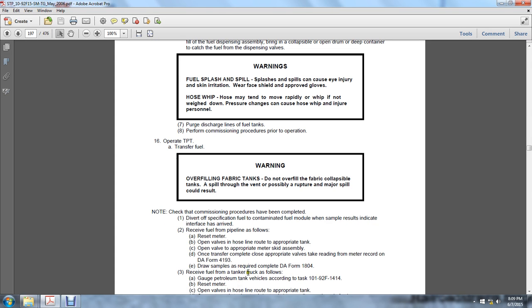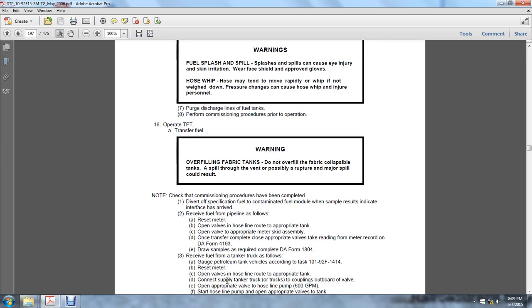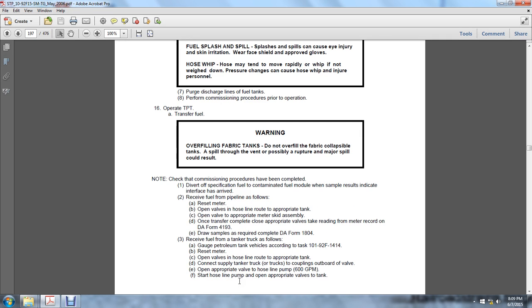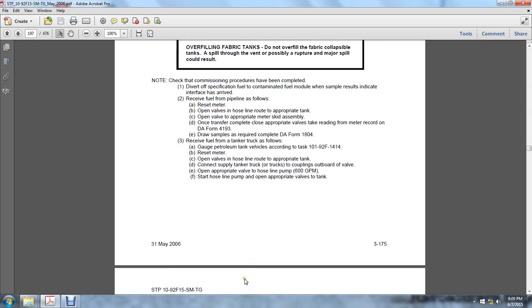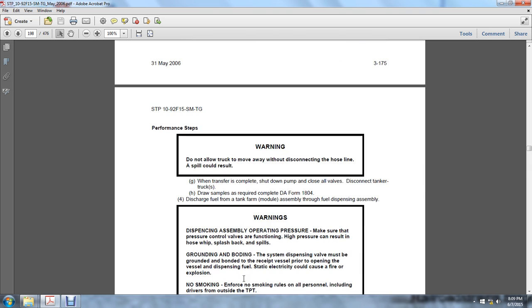Receive the fuel from the tanker truck as follows. Gauge the petroleum tank vehicles according to task 101-92F-1414. Reset the meters. Open the valves in the hose line out to the appropriate tank. Connect the supply tank truck or trucks to the couplings outboard of the valve. Open the appropriate valve to the hose line pump. The 600 gallon per minute. Start the hose line pump. Open the appropriate valves of the tank.